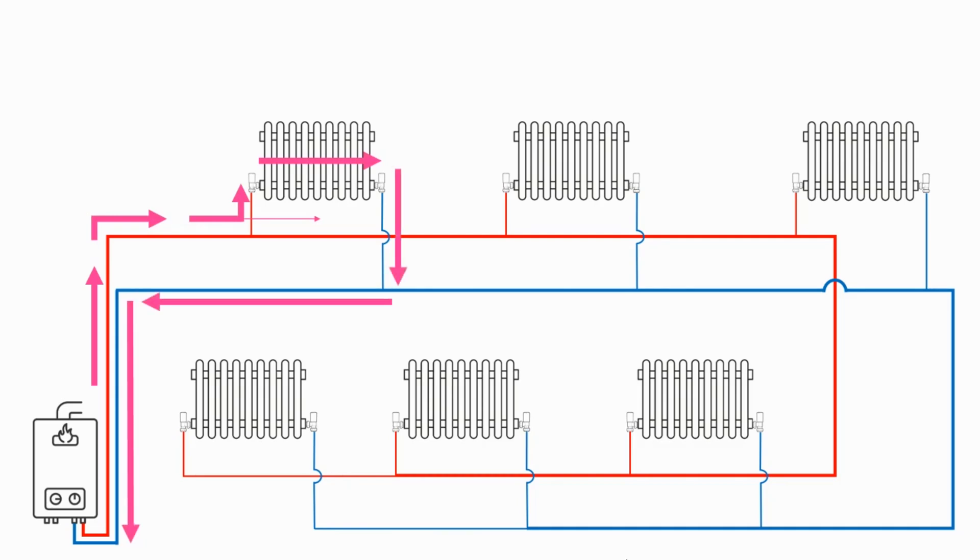This causes two main issues. Firstly, other radiators on the system don't receive enough hot water so they're unable to achieve their heat output and that will result in cold rooms. This will be particularly apparent on those radiators furthest away from the boiler or where hot water has needed to be elevated to higher floors.